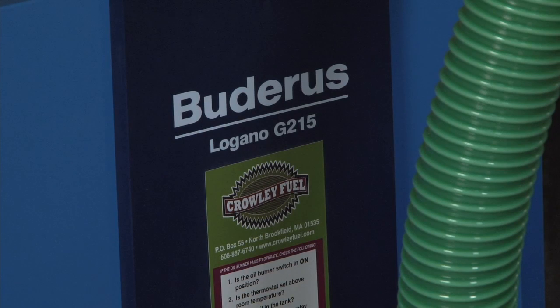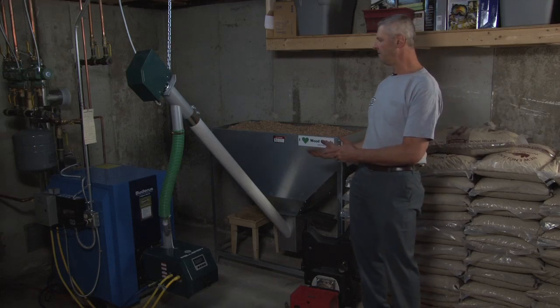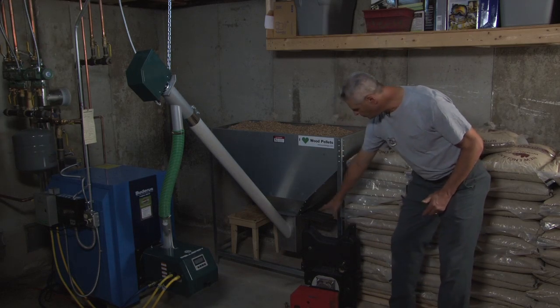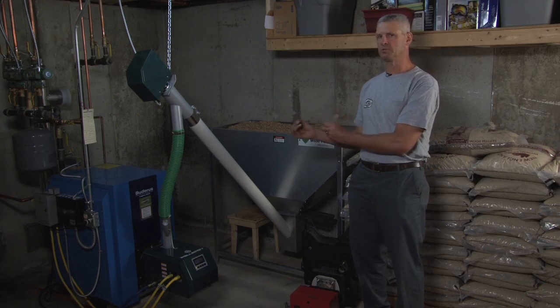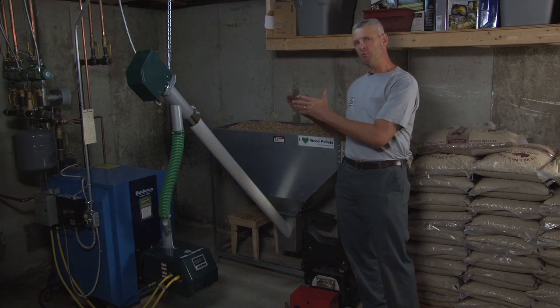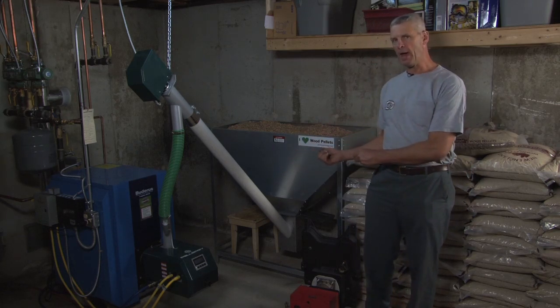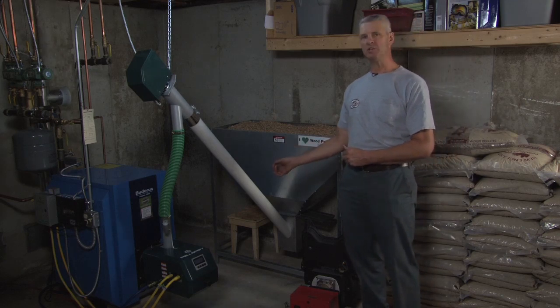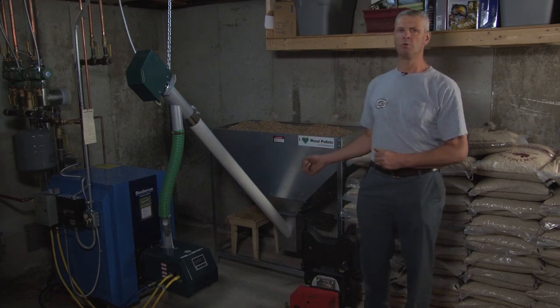This is a Buderus G215 boiler, one of the boilers that will accept the Pellergy system. The important thing is that you need to have a triple pass boiler that has a swing door, and that's what the Buderus has. This door will swing open and you'll be able to reach all of the flue passages from the front of the boiler. When looking for a boiler that will accept the Pellergy burner, it needs to be triple pass with a swing door because there is some maintenance involved — you need to clean the fly ash out periodically. Not every boiler will work with this system.